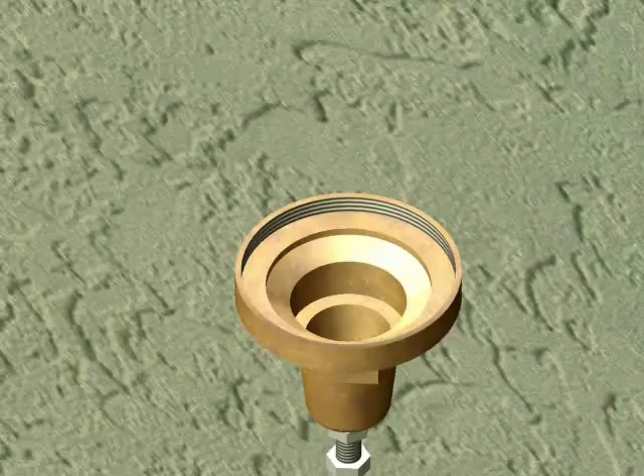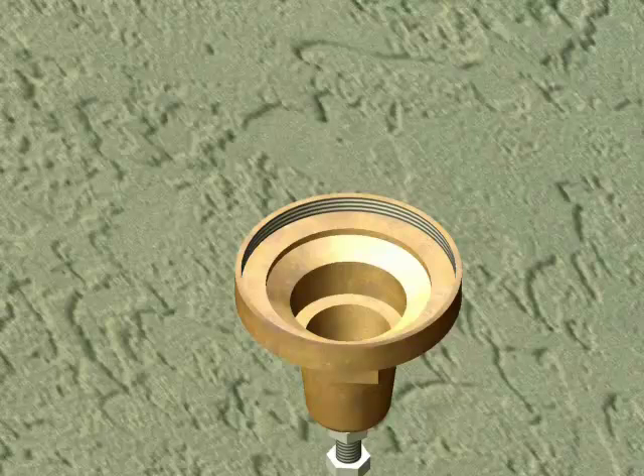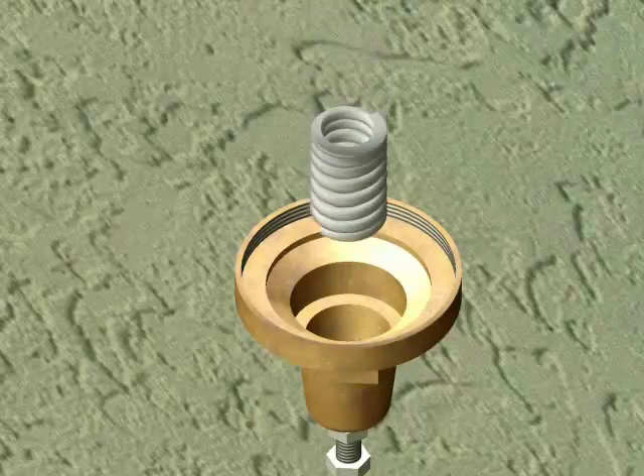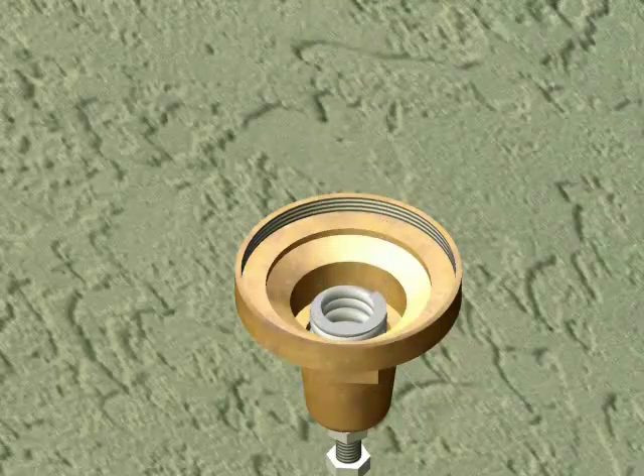If the valve is installed flowing vertically, center the spring disc on the adjustment bolt in the bell. Place the spring on the spring disc and put the friction ring into the bell opening.